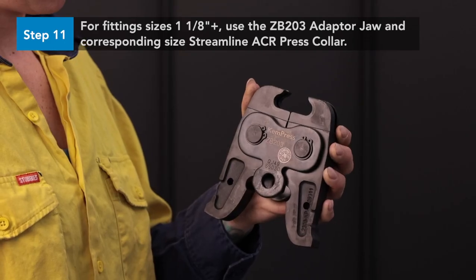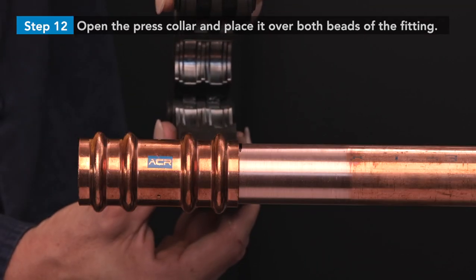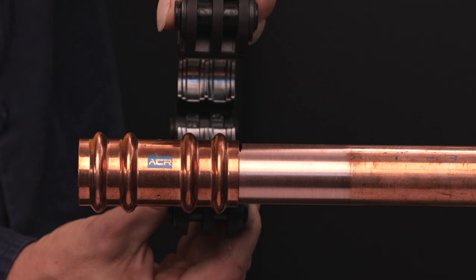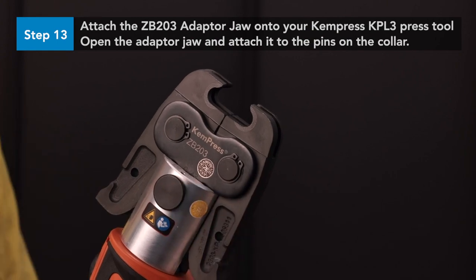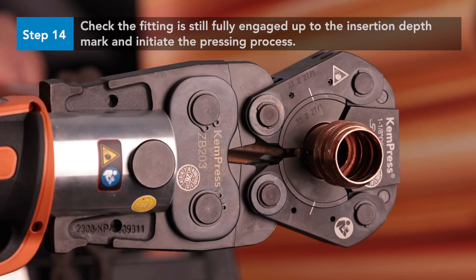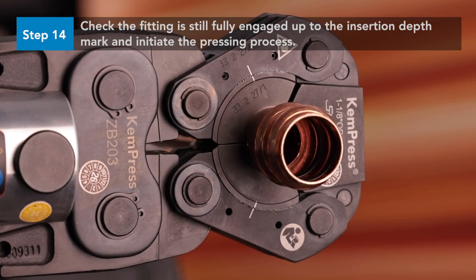For fitting sizes 1⅛ inch and greater, use the ZB203 adapter jaw and corresponding size Streamline ACR press collar. Open the press collar and place it over both beads of the fitting at a right angle to the copper tube. Ensure the two beads of the fitting fit into the two corresponding grooves of the press collar. Attach the ZB203 adapter jaw onto your KemPress KPL3 press tool and lock it by engaging the locking pin. Open the adapter jaw and attach it to the pins on the Streamline ACR press collar. Check the fitting is still fully engaged up to the insertion depth mark, and once the jaw and fitting are correctly engaged, initiate the pressing process by holding down the start button.